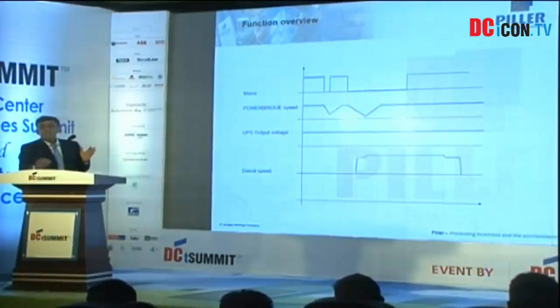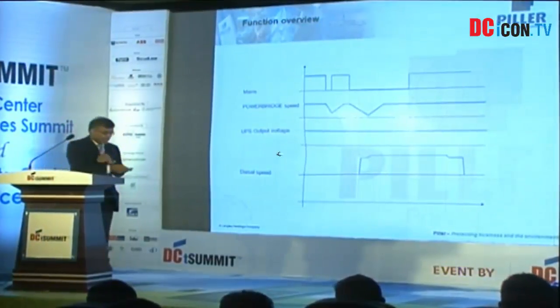There's a failure here, a short-term failure, and this is a bit long-term failure. In both these cases, the flywheel starts to discharge energy, as you have seen here. But this particular outage is too short, so you don't have to start your diesel engine. The flywheel covers, then starts to recharge again and is ready for any outage.